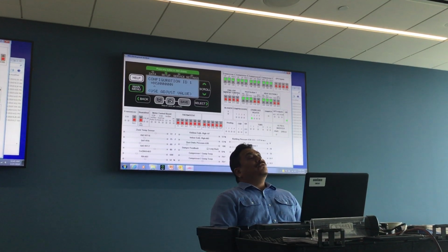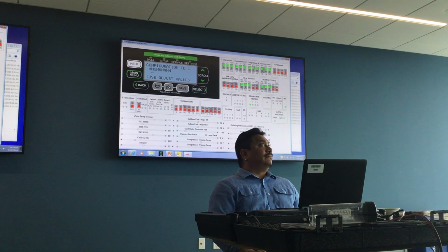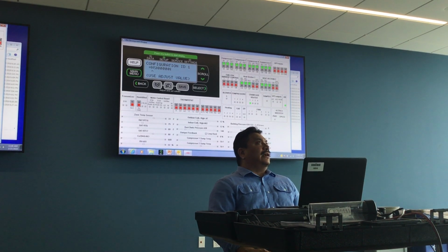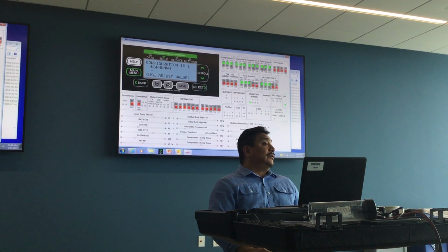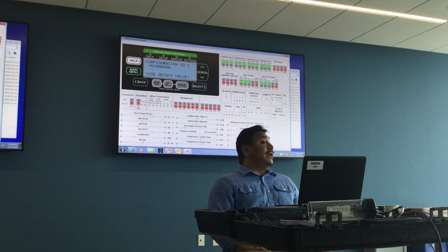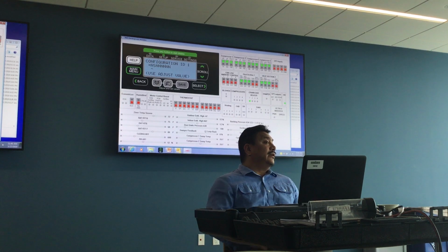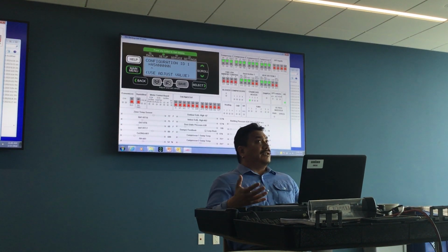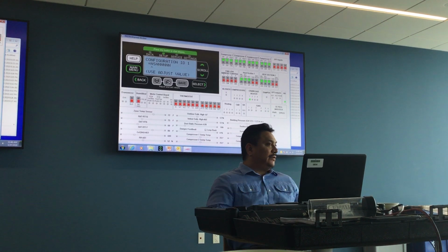I don't know that you can do it through programming yet, but it will, I think on like a 7.5, like 10 tons, okay? Head pressure has to get up to at least 375 before you see one condenser fan motor come online. So it's our way of ensuring that the compressor is running and you are getting that differential in pressure, okay? So again, the idea is that it's kind of the engineering and the efficiency built into the unit showing itself. Okay. You know what I mean?